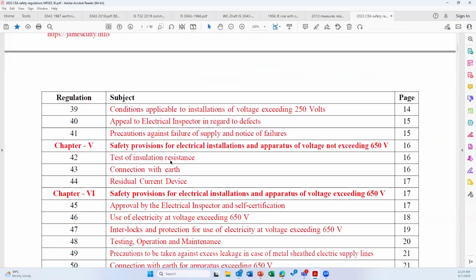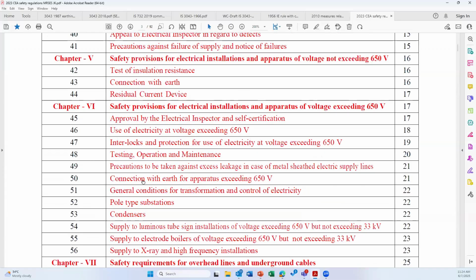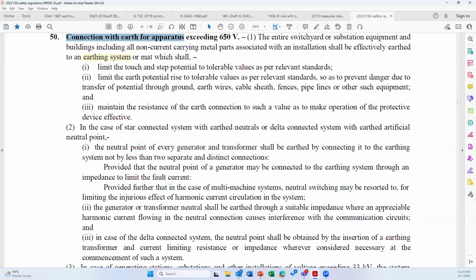Regulation 50, which is earthing above 650 volt, connection with the earth for apparatus exceeding 650 volt. Now, read here. The first requirement is to limit the touch and step potential to a tolerable value as per the standard. The idea is people should not get shock. You have to ensure that the touch and step voltages are within certain limits. As a result, people don't get shock.